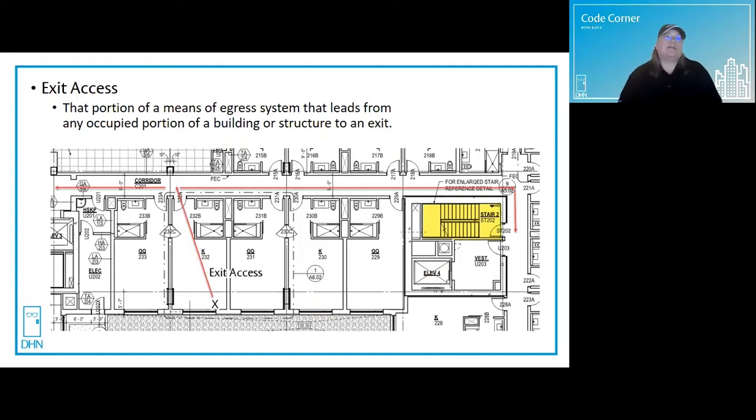The exit access is that portion of a means of egress that leads from any occupied portion of a building or structure to an exit. The exit is highlighted in yellow. The exit access from any room or space, you can see the X follow that path. Once you get into the hallway, the corridor, you're still in part of the exit access until you reach the door at the stair or the door that leads directly to the outside.